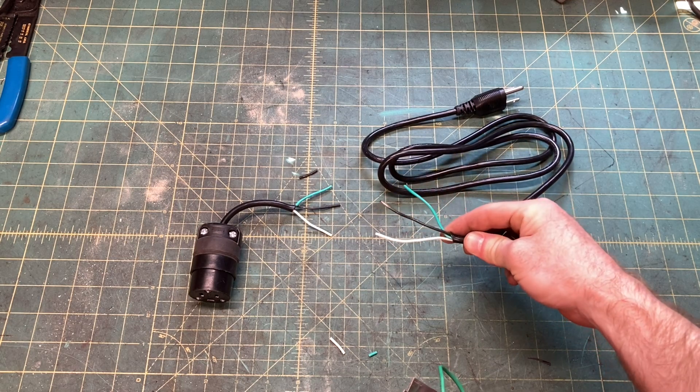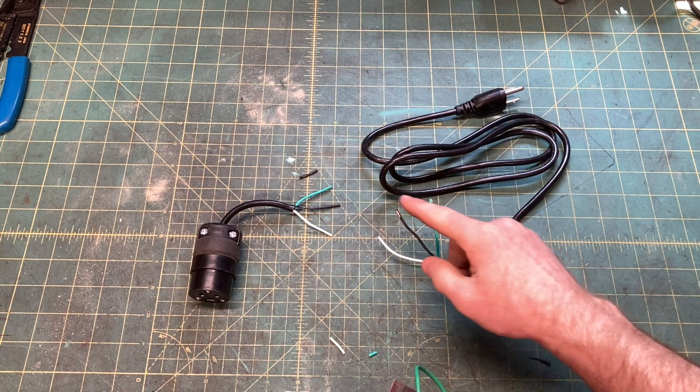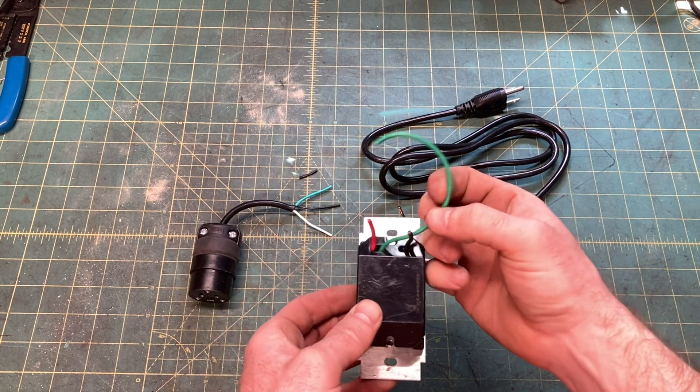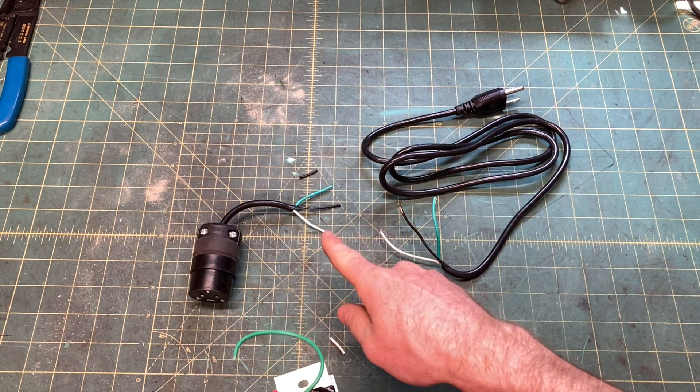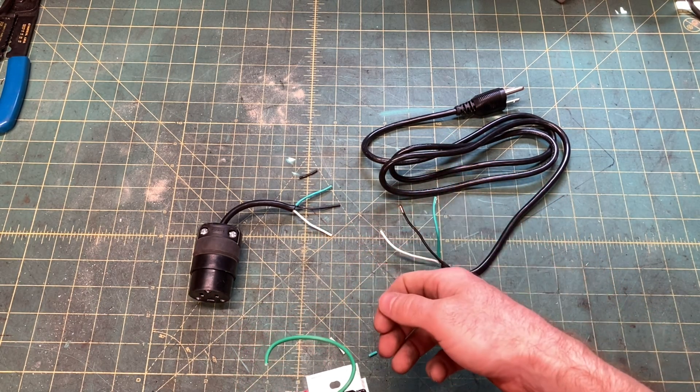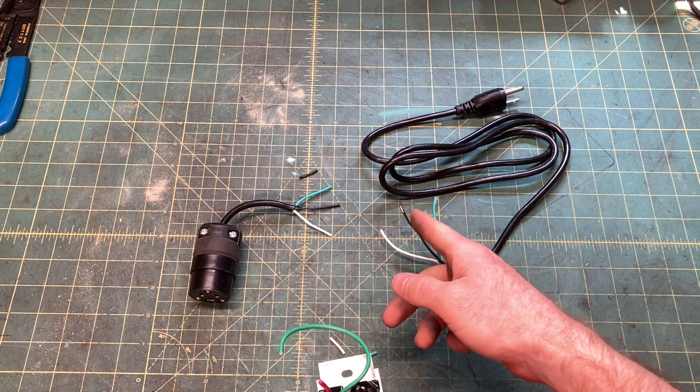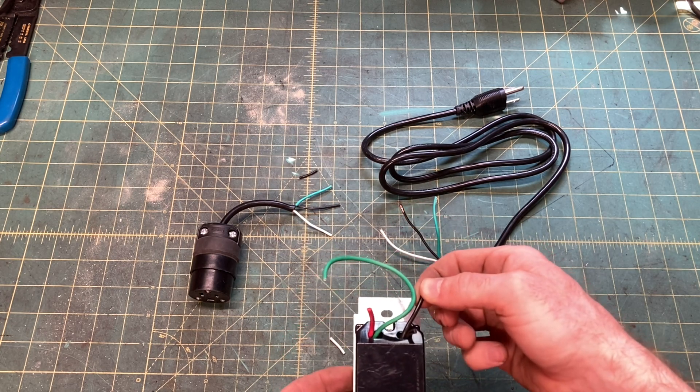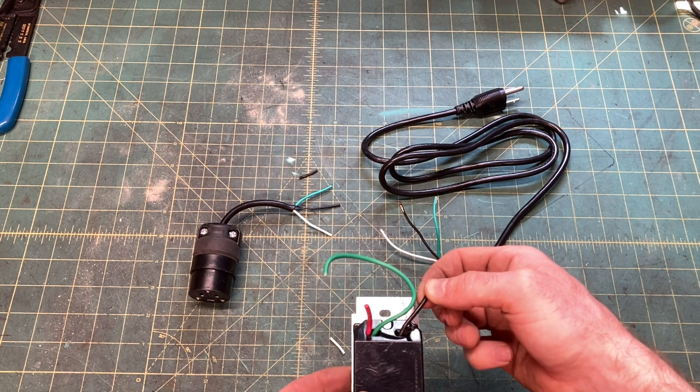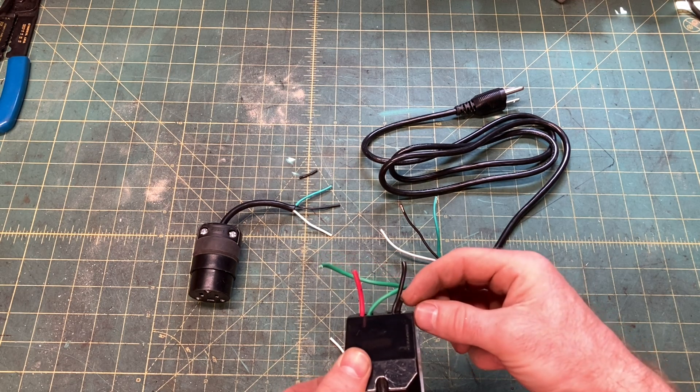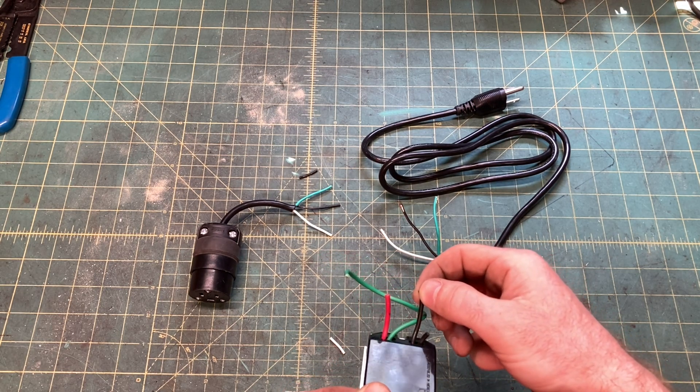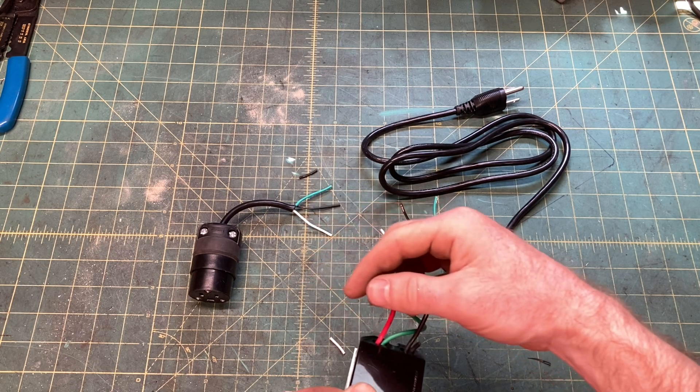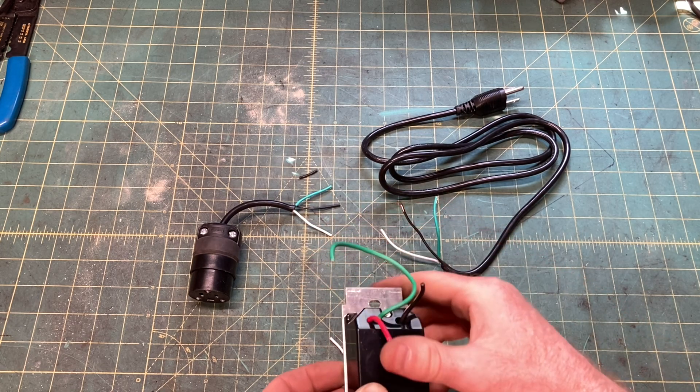Wiring is simple. All three ground wires are going to get tied together and ideally grounded to the box, but eh. Neutral goes straight through, so hard to mess that up. The black line wire goes to the black wire on the switch. Just make sure if you bought a three-way dimmer that you use the wire labeled line and not the one for the three-way function. The black load wire goes to the red wire on the switch.